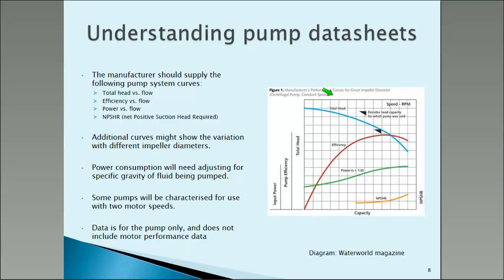At the bottom there we have a yellow line, the NPSH — net positive suction head. If you're going at very high flows and the pressure at the inlet starts to get low, you can get bubbles, which reduces the efficiency. When the bubbles burst, you get cavitation — that starts to erode the pump and the pump makes a horrible noise. So that's something physical you need to check when finally selecting the pump to use.